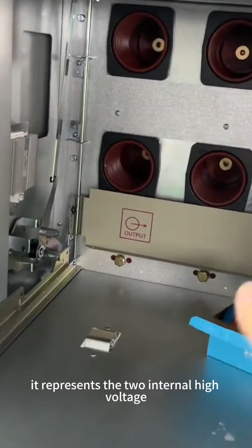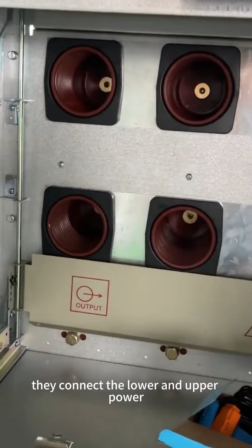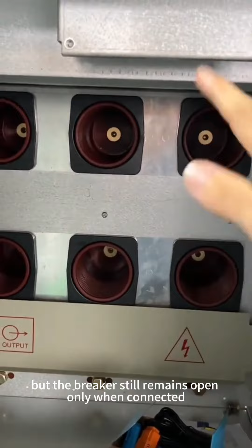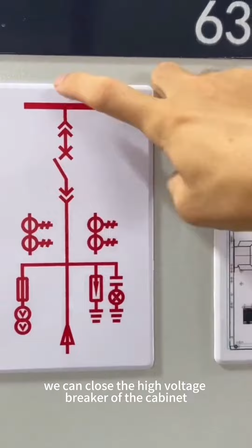You may wonder about the meaning of the double arrow symbol. It represents the two internal high voltage circuit breakers, which can be pushed in or pulled out. When pushed in, they connect the lower and upper power supplies through the high voltage breaker, but the breaker still remains open. Only when connected first are the lower and upper power supplies joined together, and afterward we can close the high voltage breaker of the cabinet.